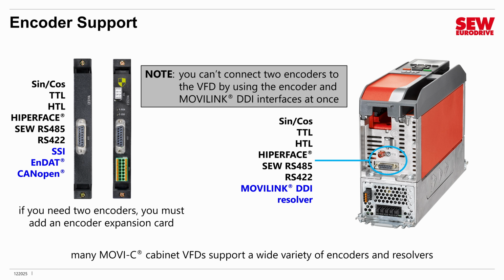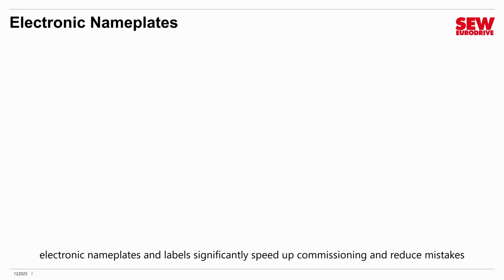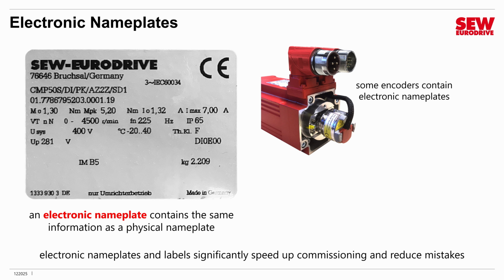Closely related to encoders is something called an electronic nameplate. An electronic nameplate, which also goes by the name electronic label, is the equivalent of your traditional physical nameplate on the motor. It contains the same information, the electromechanical information, like the motor's voltage, current, frequency, nominal speed, and power factor. The VFD needs this information in order to be commissioned.